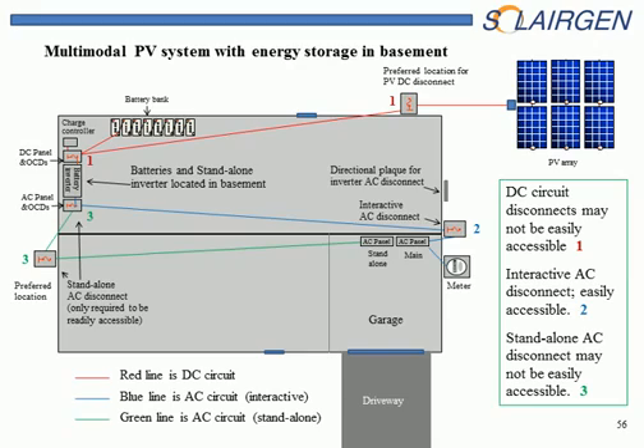So the high voltage DC power is stopped at the DC disconnect. Number 2 disconnects the interactive AC power from that inverter. Number 3 hopefully is outside, but it may not be. It may be inside in the basement. That would be the AC disconnect that shuts down the backup panel, the critical loads panel, this standalone AC panel. So that may or may not be outside. If it's outside, you've got all the AC power turned off, and then if you shut down number 1, you have the DC power shut down, except for the battery bank, which still has 50 volts and potential power in that. So if you know where that is, you can just be mindful of that potential in the basement.